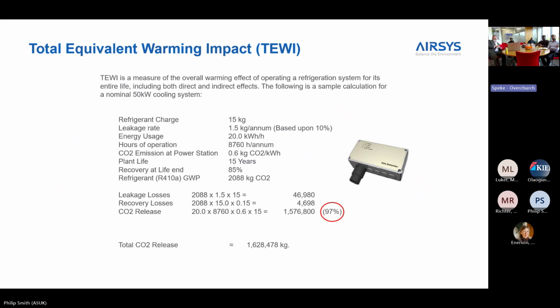But we then come to what, have you heard of the TEWI, total equivalent warming impact, which basically looks at the life cycle of the product itself as a combination of both the energy that's used, the CO2 generated, and the effect that the refrigerant use has on that product. So this is a 50 kilowatt unit. It's got 15 kilograms of refrigerant in it, factoring in a little bit of leakage each year across its life cycle and a little bit of loss when you scrap it. And then the energy used to run the system.